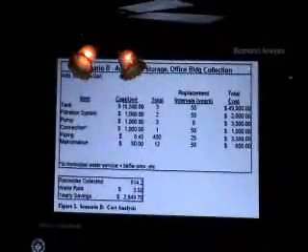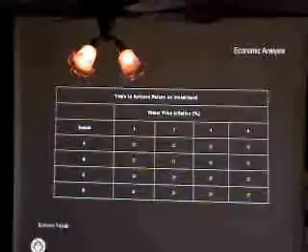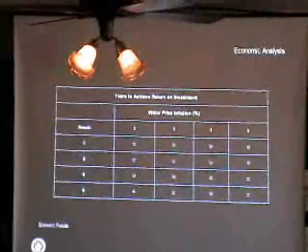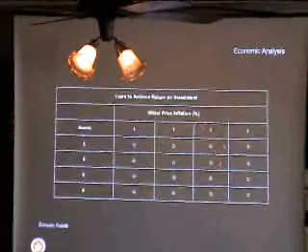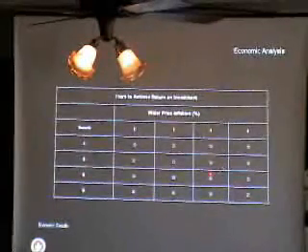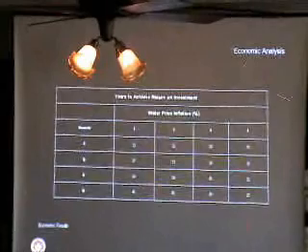As Ken mentioned earlier, the savings that we ended up with is about $2,800 per year for water savings. This takes into account the water rate of $3.50 per 1,000 gallons, if you're buying it from a municipal system, and the amount of water collected. So we're collecting almost a million gallons of water a year, and you're still only saving about $2,800 per year. With that, we figured out a basic set of years to make your money back on the system. Considering water price inflation, which right now I believe is about 5%, which is a fairly conservative estimate at the moment, even with scenario B, which is the most effective site, you're still looking at about 18 years before you ever make any money off of this water system, which still begs the question of why you would use rainwater systems as opposed to municipal systems.